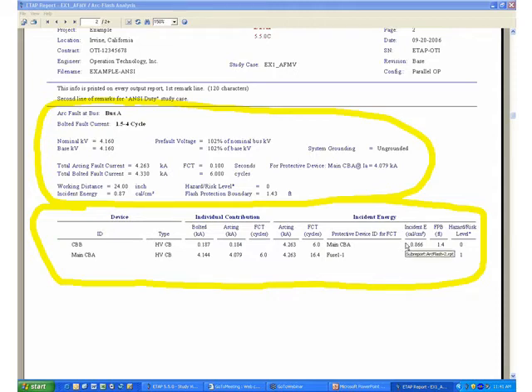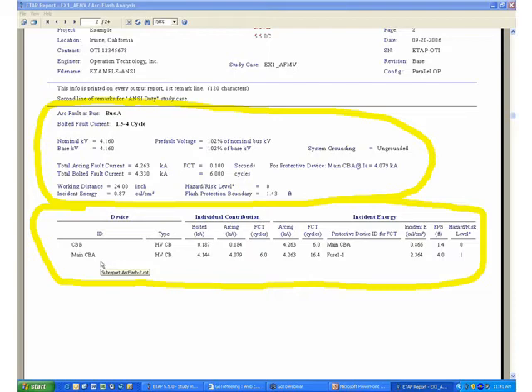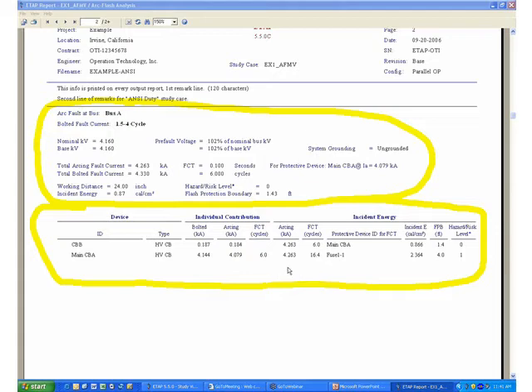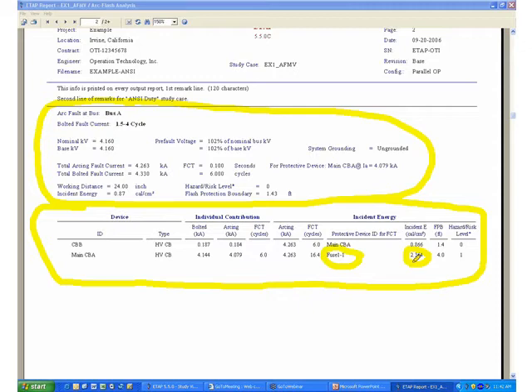However, if you were working on the Main CBA, the program has determined a more conservative solution, assuming that Main CBA itself cannot trip this fault and therefore you will have to rely on an upstream protective device to trip that fault. In this case the primary protection will come into play, which is Fuse 1. So the program automatically selects Fuse 1 as the protective device that would trip the fault on the line side of Main CBA. Therefore for a fault on the line side of CVA Main CBA, the incident energy release will be 2.364 calories per centimeter squared and the hazard risk level will be increased now to a category 1.